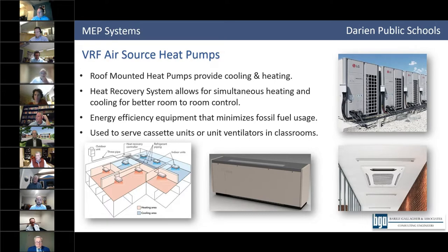In this slide, upper right, those are your condensing units, and all of that equipment will be on your roofs. Lower right is an example of the cassettes I talked about earlier, which will be in each classroom or even smaller spaces. The middle one on the bottom is a unit ventilator. Where you have existing unit ventilators, we thought it most cost effective to take the old one out and put in a new one with a hot water coil and a VRF coil, so that one piece of equipment will be redundant, you can run it on electricity, hot water, or gas.